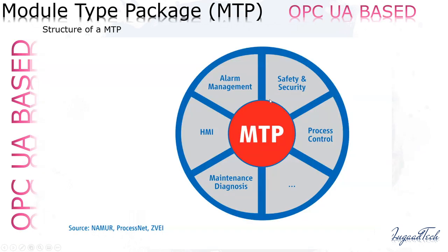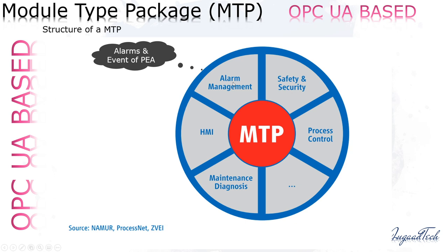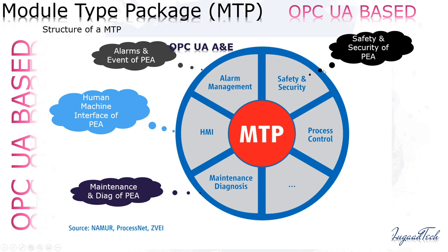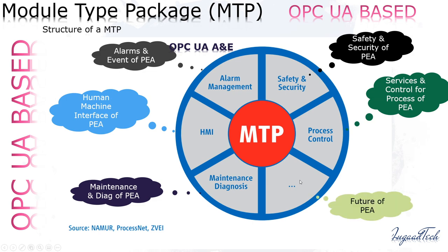So what NAMUR did — they introduced a new standard based on a standard architecture, the OPC UA architecture, and divided the whole thing into different small modules: alarm management, HMI, maintenance and diagnostics, safety and security, and process controls. Alarms and events of a PEA system will be based on OPC UA alarms and events. The HMI module handles the human-machine interface of a PEA. They have also kept some open slots for future PEA modules to be introduced.